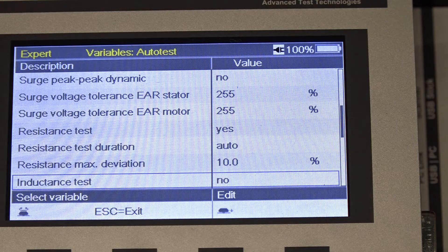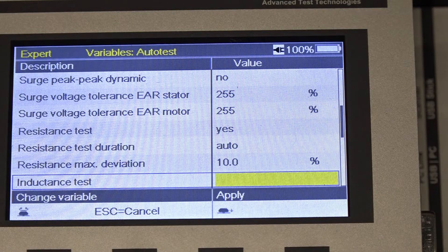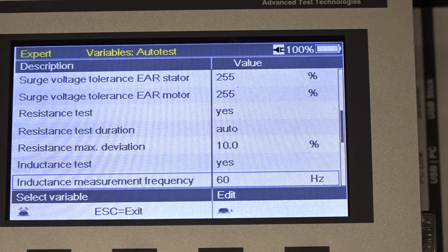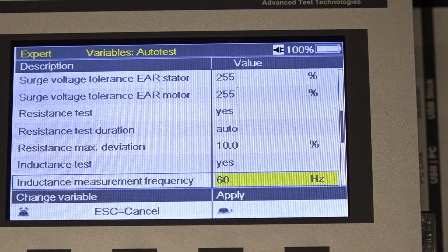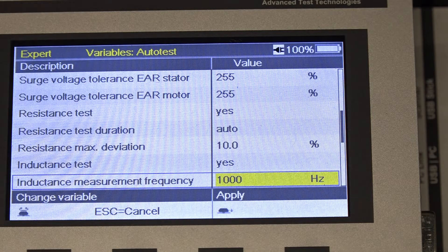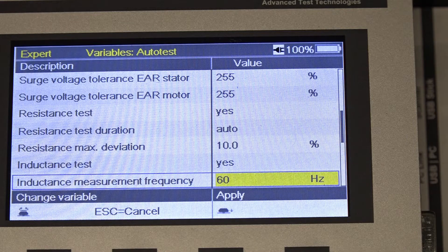So there's our inductance test. We'll press the wheel and then select yes to turn it on. The inductance test will run at 60 hertz, just so it matches the US standards. You do have a number of different choices here, but I would suggest you stick with 60 hertz.